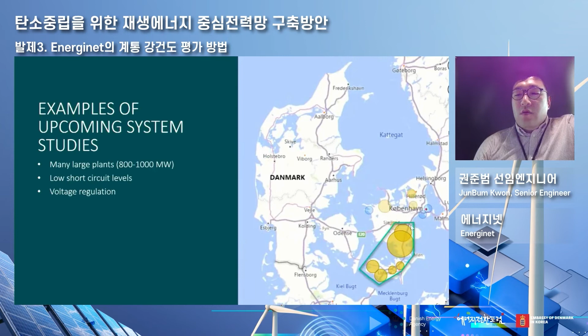So what I'd like to emphasize is that there are many ways to conduct short circuit calculation, but accurate representation of short circuit contribution from inverter-based systems will become more and more important as the power system is increasingly governed by inverters. The best way to characterize short circuit characteristics is to use data directly from vendors as part of grid connection requirements, and use that data to build models in the TSO's database. If it's limited to ask vendors for data for some reason, such as plants or HVDCs already under operation, the proposed approach would provide similar results and give an overview of short circuit contributions of vendor-specific models.